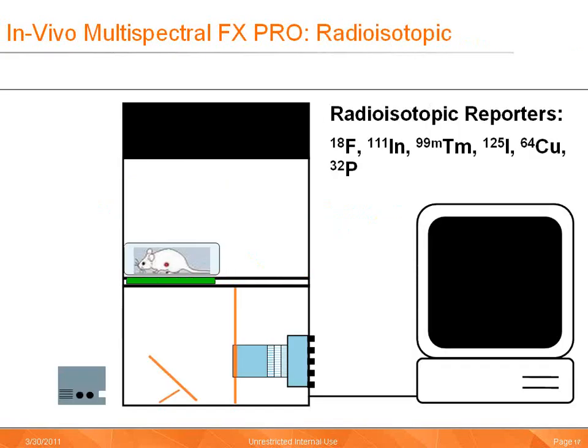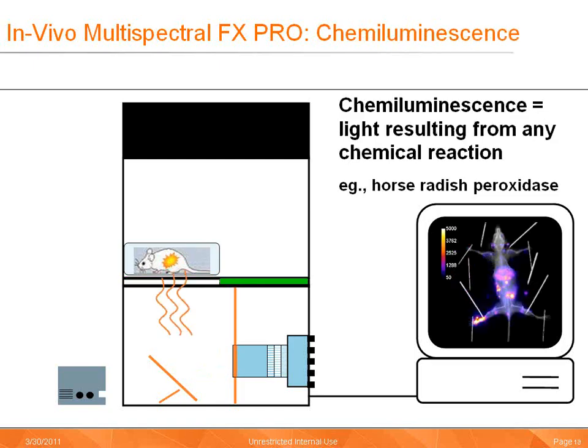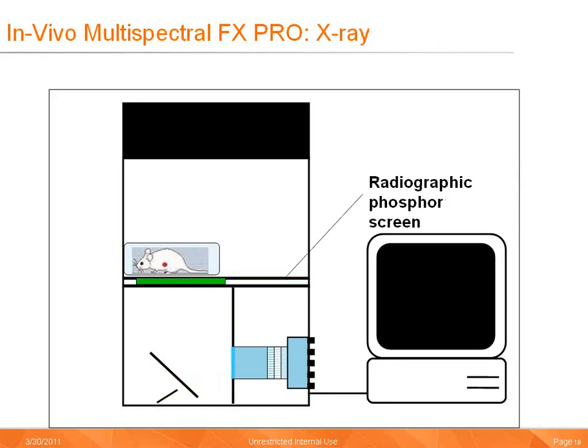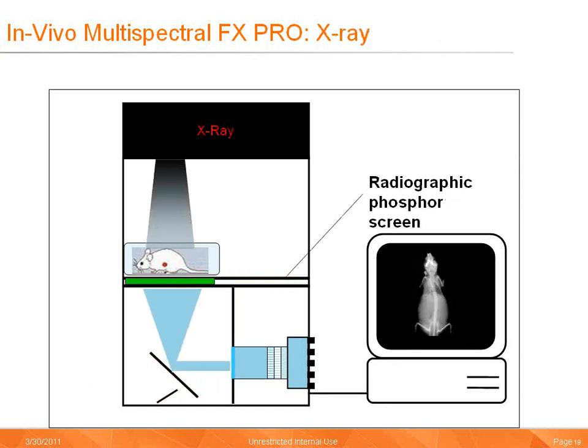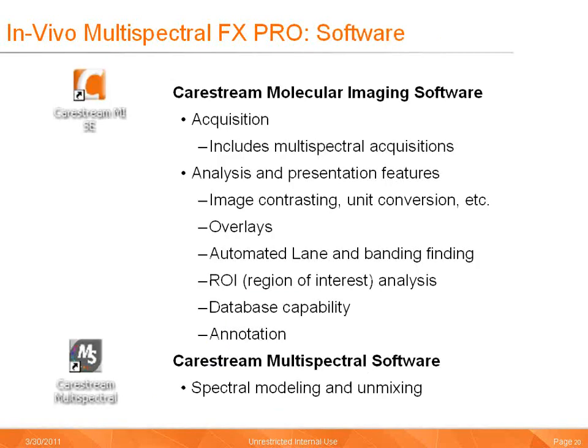For radioisotopic detections, a phosphor screen slides between the sample and the detector, and the energy is converted to photons for detection. For luminescence detections, the sample is held in a light-tight environment and detection occurs again at an inverted right angle. For X-ray detection, a phosphor screen slides between the sample and detector; X-ray is applied overhead and the phosphorus converts energy into photons for detection. The in vivo multispectral FX system employs two software packages: the CareStream Molecular Imaging software for driving acquisitions and data analysis, and the CareStream Multispectral software for post-acquisition modeling, unmixing, and image presentation of multispectral data.